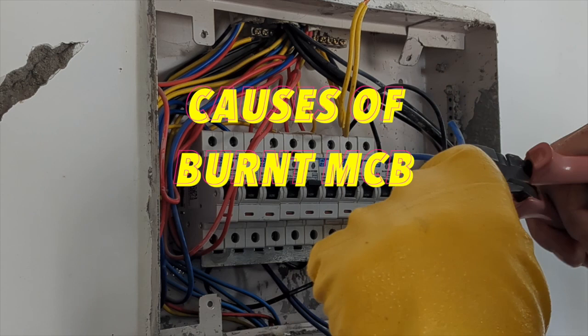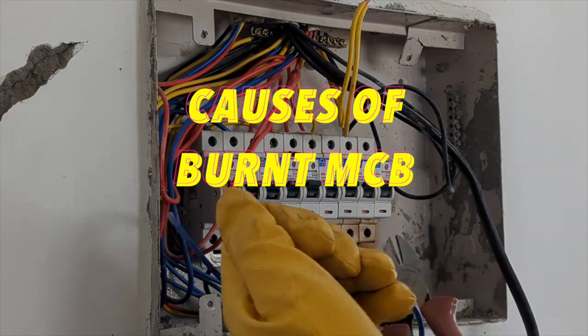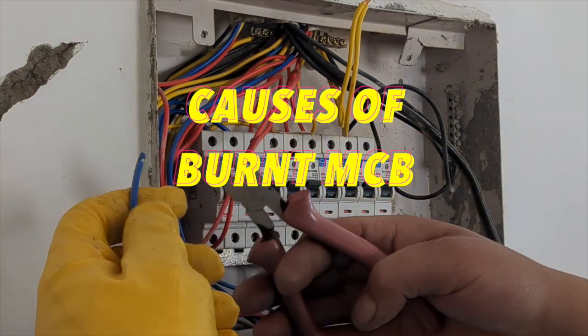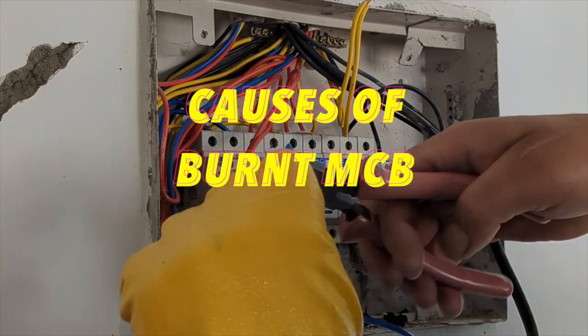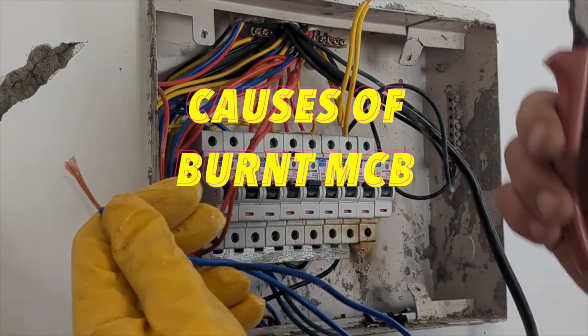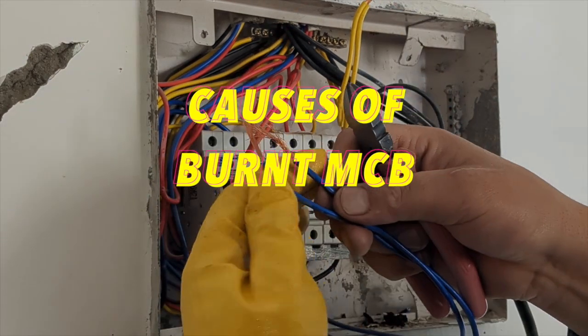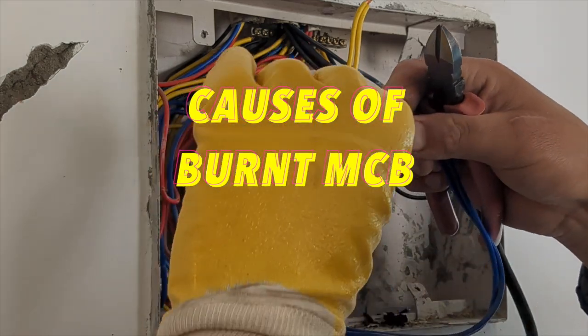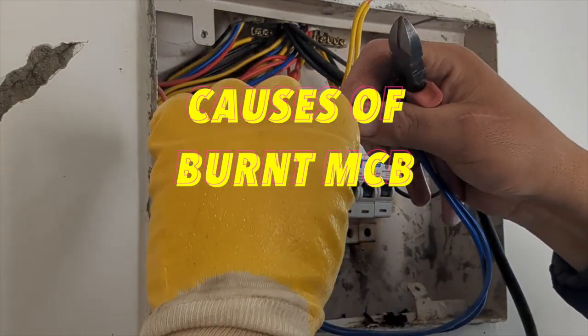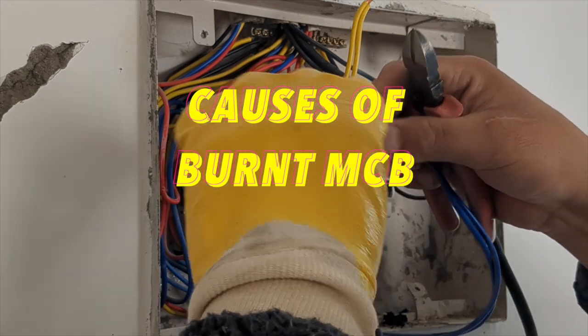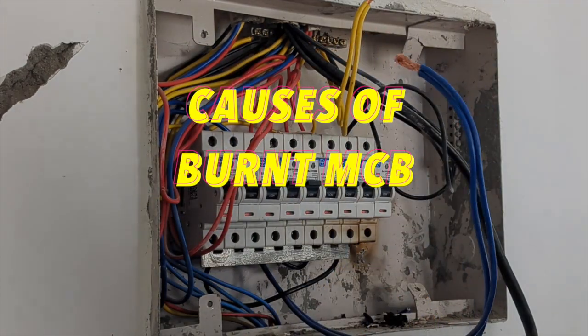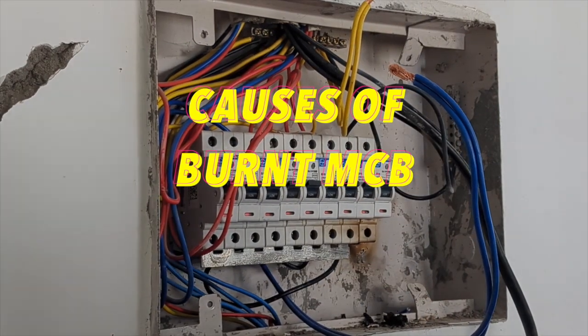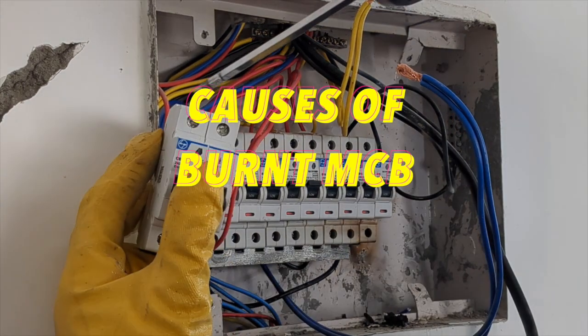Now, let's talk about what causes circuit breakers to burn. The most common cause is overheating, which can occur due to overloads, power surges, or arc faults in your system. Any of these events can suddenly overheat your circuit and possibly cause the breaker to heat up and burn, resulting in a tripped circuit breaker. Another cause can be a faulty circuit breaker. Sometimes a defective circuit breaker won't detect a fault if it happens, which can lead to a burnt breaker.